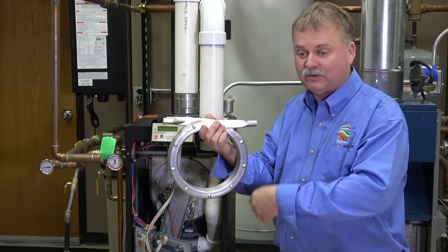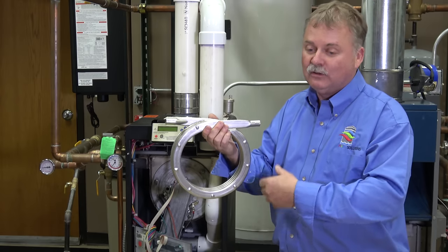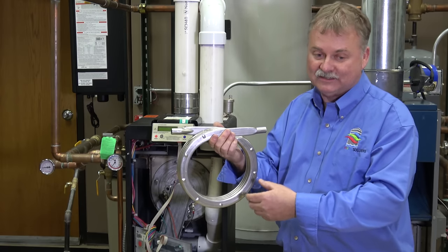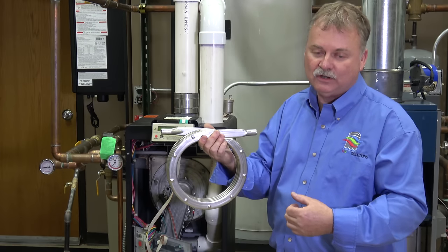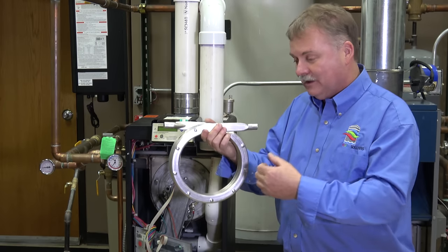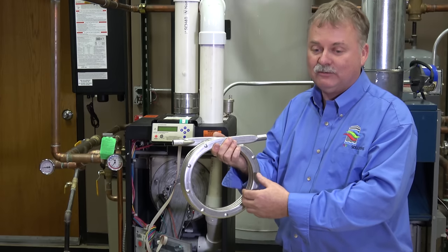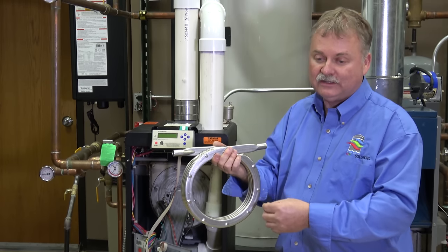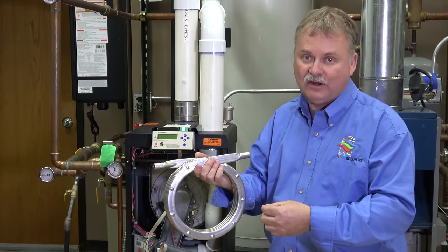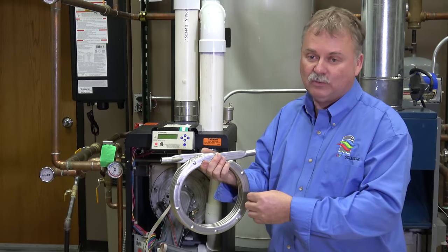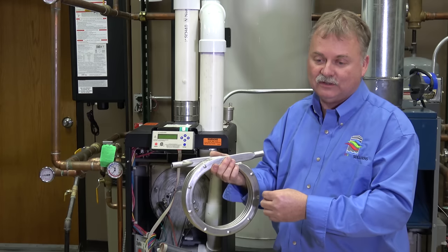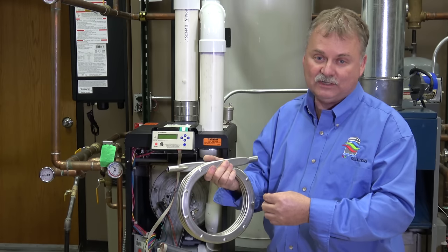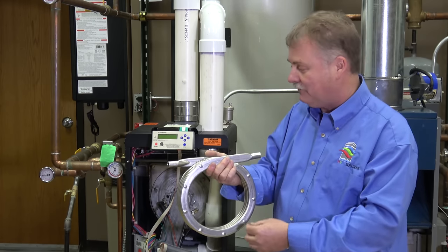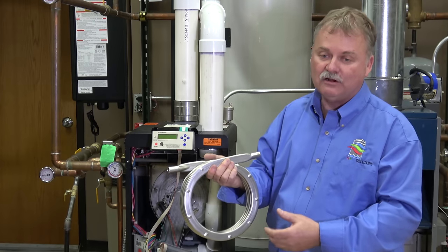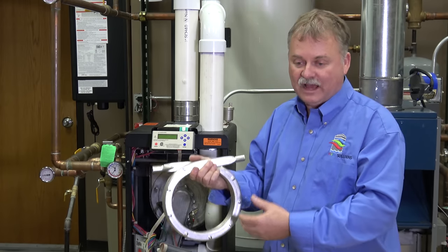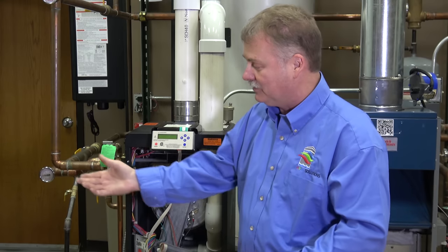It gives us a lot of heat transfer very, very quickly. Works well on larger systems, that kind of stuff. Small, big zone systems, all right? The kicker is, you've got to be careful with these, because if you try to turn little zones on and off, you're going to be cycling this boiler. And as we've discussed in other videos, cycling is no good for any piece of equipment. So what some manufacturers have come up with is what we call a large mass high efficiency boiler. And that would be this one over here.